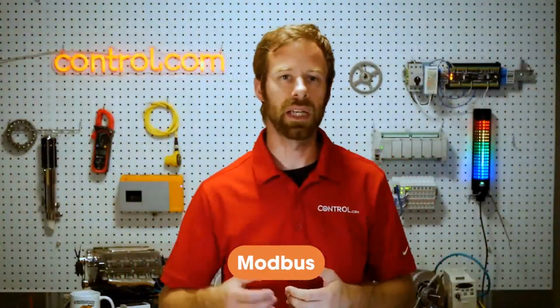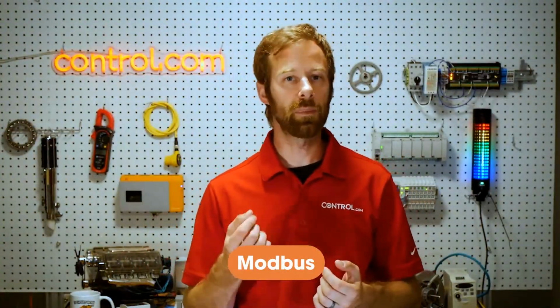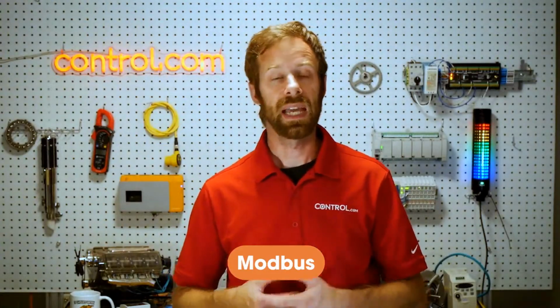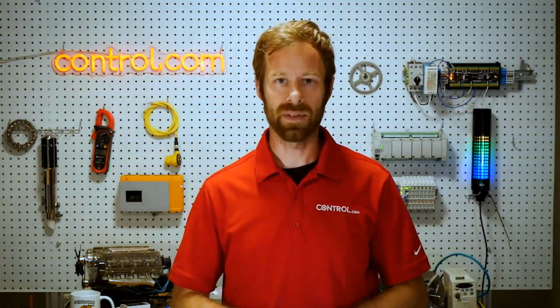Modbus is a system of being able to read and write discrete bits, which are on-off values, and analog values, which are usually called registers, meaning that they can be any sort of integer information, even if it's not an analog input. But we can transmit those with a very consistent set of commands. And what usually happens is this Modbus command and address, so we send a command, what do you want to do, and where do you want to do it to? I want to turn a bit on, and I want to do it in this location or at this address.